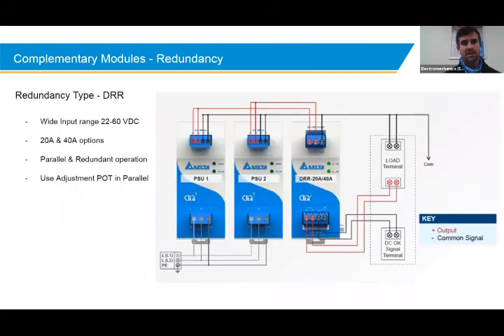Another complementary module is the redundancy unit. You've got a 20 and a 40 amp option, with a 22 to 60 volt DC input in this redundancy module. So 24 and 48 volt versions will be supported. It's a parallel and redundant operation. So if you would like 2 10 amp power supplies helping each other out, you could configure it in a parallel operation. If you're doing it in parallel and you want the power supplies to assist each other, then it's important that you make sure that the voltage potentiometers and the output voltages of each power supply are very close to each other, so that one doesn't carry more load than the other.